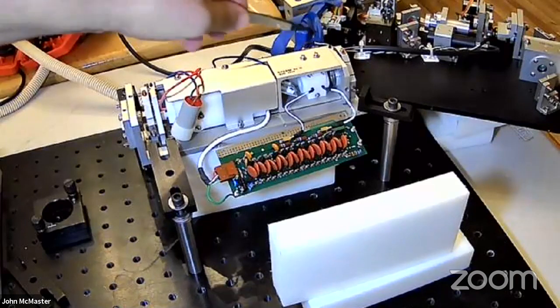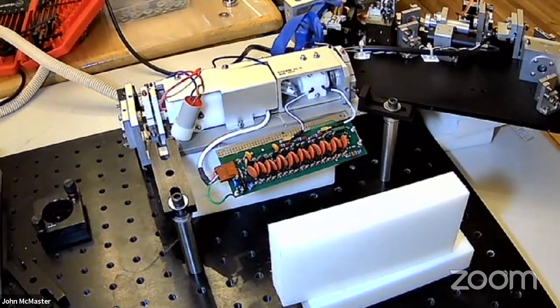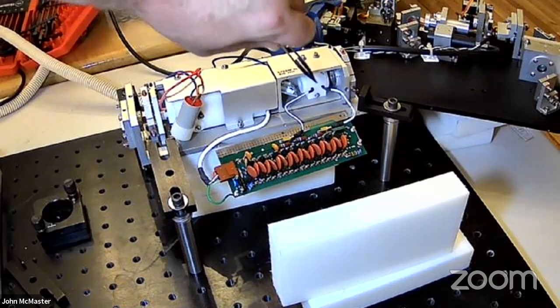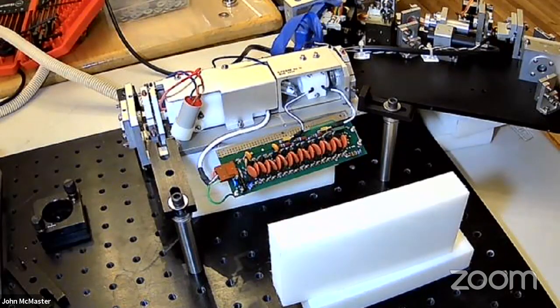Okay. So with that in mind, the next question is, the main failure of these lasers turns out to be that this element right here, the so-called optical cell, those seem to either fail or this whole cavity as a whole gets misaligned. In my laser, for example, this is my old laser right here. This thing had a failure on a gasket, and I'm jokingly calling it the headlight fluid leaked out of the laser. So when you want a really clear optical surface, you may put something called immersion fluid in there. And what that does is it goes between two optics and makes it optically clear between them, so you don't have any boundaries.